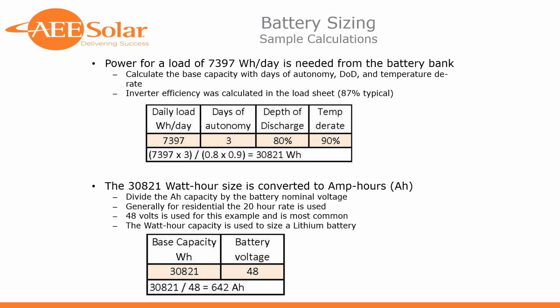So this is a slide you put together for us, Brad, with just some real simple sample calculations. If you want to walk through that, I've got, I think, 2 more slides, and then we'll have some time for some questions. Okay. So I just took a sample load of watt hours per day and a calculation to figure out how you would size a battery bank for this, particularly for an off-grid system, but it could be used for other systems. So you've got watt hours per day, you've got the number of days you want that to go. That could be hours also. The depth of discharge you want to take the batteries down to, and of course temperature derate. And so you're just multiplying the load by the time that you want it to run, and then dividing it by the derates of the depth of discharge and the temperature, and it comes up with your gross battery size.